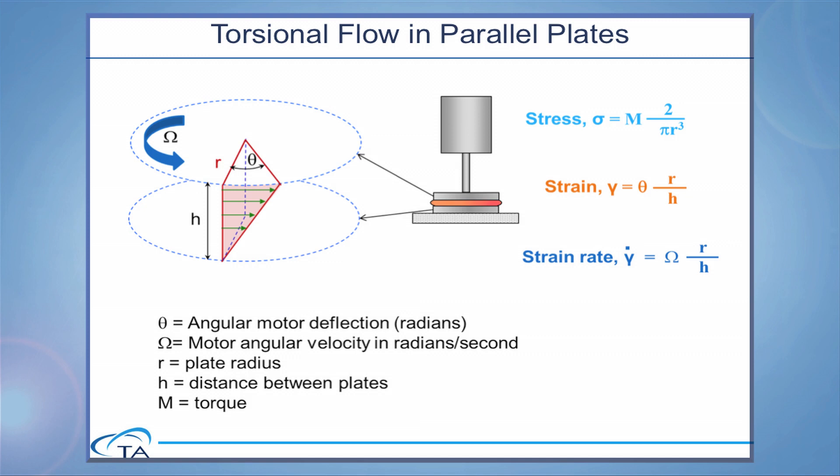If we look at the main rheological parameters of interest - stress, strain, and shear rate - all are directly dependent on the area in contact with the sample, normally the surface area of the geometry, and thickness of the sample gap.